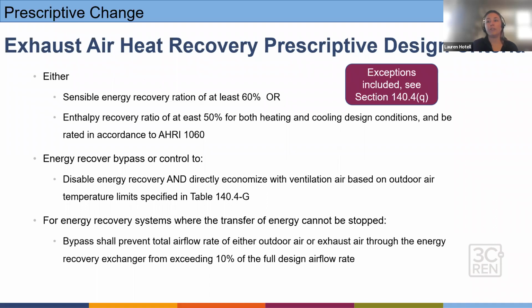You can use an energy recovery bypass or control to disable the energy recovery and directly economize with ventilated air based on outdoor air temperature. Take a look at table G for those temperature limits. And then for energy recovery systems where the transfer of energy can't be stopped, you need to have a bypass that can prevent total airflow rate or outdoor air or exhaust air through the energy recovery exchanger from exceeding 10% of the full design airflow rate.